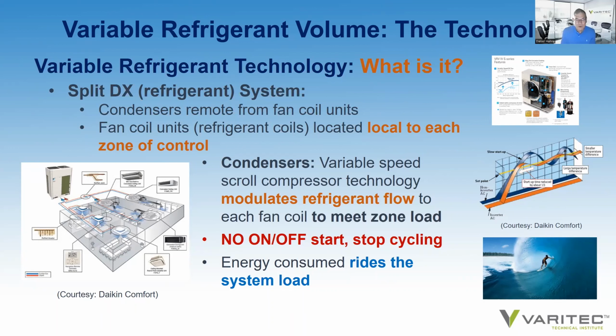Variable refrigerant brings the refrigerant down to the building zone, so it's local to the space. The condensers used in a variable refrigerant technology are variable speed. So instead of on-off cycling, they actually effectively ride a building load. They can deliver only that amount of refrigerant necessary to cool or heat a space, as opposed to cycling compressors that result in a high current inrush when you go through a start-stop cycle in a conventional DX unit. Consequently, variable refrigerant systems using variable speed compressor technology and also variable speed fan technology allow for effective riding of the building load, so the building only consumes that amount of energy at any given time of day, at any given time of year, local to each zone.